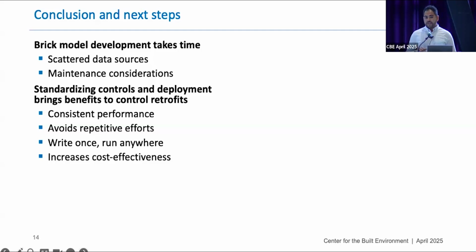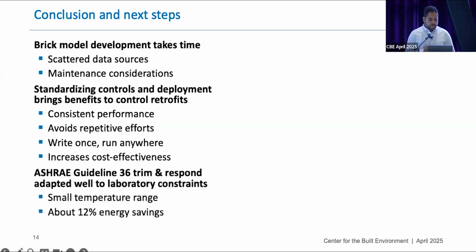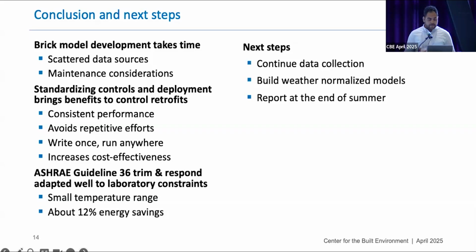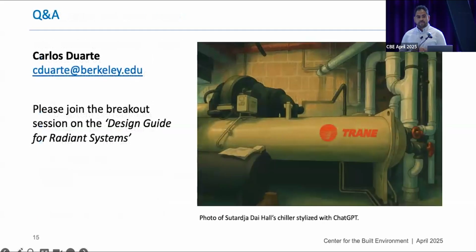We just write one application and can run in multiple buildings, which overall increases the cost effectiveness of deploying these control systems. And we saw that the ASHRAE Guideline 36 trim and response adapted well to laboratory constraints. We saw small temperature increases for the chilled water temperature, but we got pretty good savings, which amount to 12%. So we're still collecting data to build weather normalized models to figure out what is the savings potential for a whole year. And we're going to detail all of this in a report that is due by the end of the summer. So if you have any questions, I'll take them, and thank you.